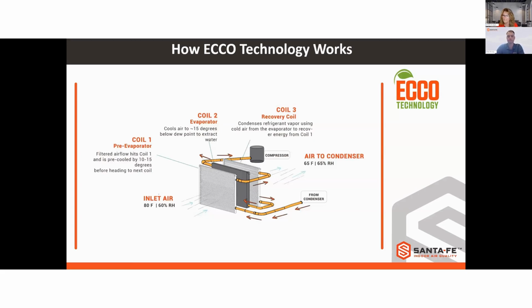Do you have anything to add on that, Dan? No, I think the amazing thing about this technology is just the compactness of the size, right? That air-to-air heat exchanger was great, but bulky. This really takes that and shrinks it down and is very efficient to build. So it's a great way to get that efficiency without adding a lot of complexity to the system. And this first coil and third coil are microchannel coils, correct? Yep, coated microchannel, so we still protect them, but there shouldn't be any water on them. But we want to make sure that they're protected because they are in the airstream.